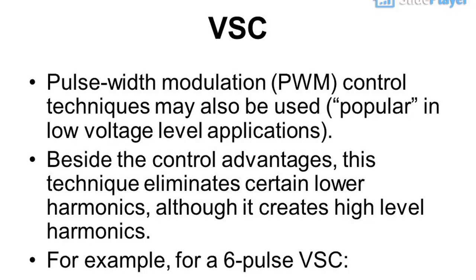VSC: Pulse-Width Modulation (PWM) control techniques may also be used, popular in low voltage level applications. Beside the control advantages, this technique eliminates certain lower harmonics, although it creates high-level harmonics.